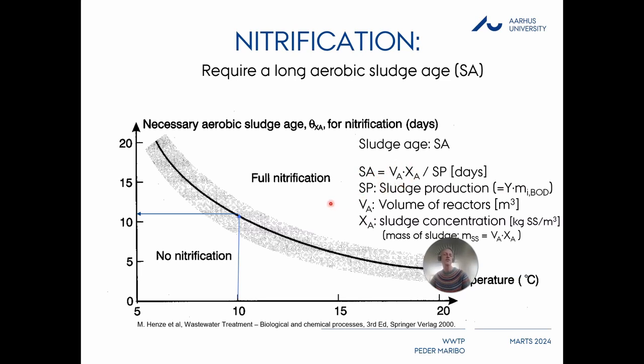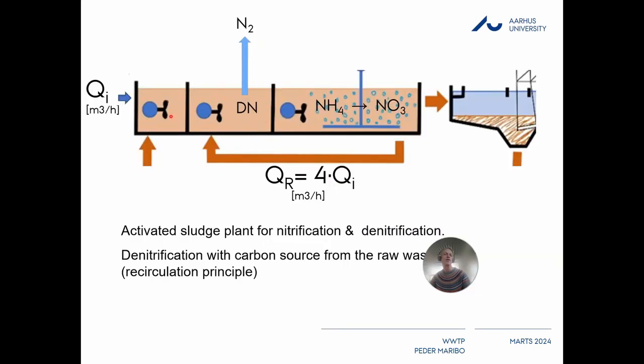This is only for the nitrification — we also need additional volume for the denitrification compartment. Including nitrogen removal in the design boosts the size of the plant by a factor of 3 to 4 in terms of process volumes, which will of course cost more money to include in the process design.